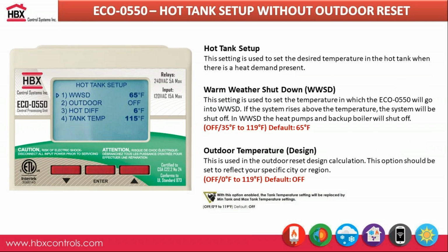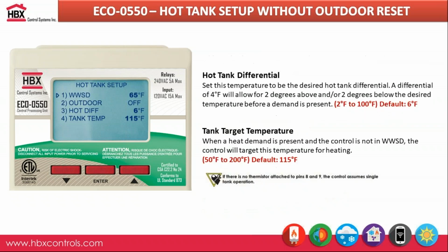So again, in terms of your tank setup, we can have it with or without outdoor reset. If you were not doing it with outdoor reset, you would simply enter the tank temperature that you always want it to be for heating and cooling. You can put a differential on your tank. And the way we do our differentials is that whatever temperature you put in, we cut that in half. So say you were to put a differential of 10 degrees, it'll be 5 degrees below and above that tank temperature target on there. Here, if you were to set it to outdoor temperature off, it automatically says that.